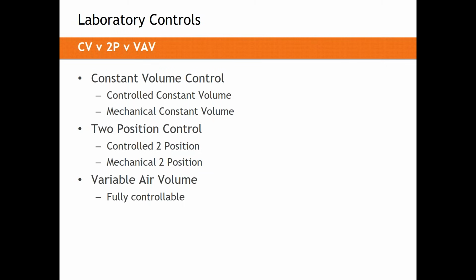So I'll show an image on the next slide right away here. But if you take all of the controls and electronics off and you physically fasten that valve into place, so you test it and you set it up for 500 CFM and you lock that into place, without the use of electronics, you can maintain that set 500 CFM. So if you have a biological safety cabinet in a compounding pharmacy, or you have a fume hood that's constant volume in a laboratory, or even an extremely simple retrofitted space that just needs to maintain a set flow, it needs to be quick and dirty, you can use a mechanically set constant volume device in that space.